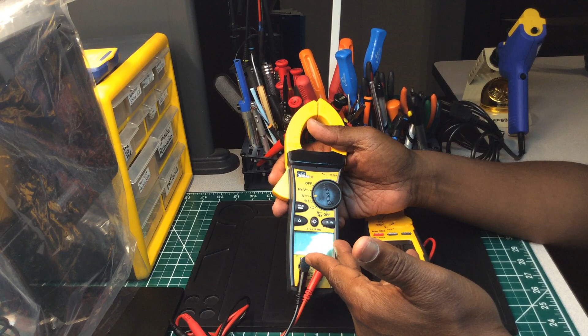You have capacitance, ohms, continuity, amps, and hertz, and relative mode. You have min max, hertz, and capacitance again — that's the selector switch right here. You have inrush here on the side, that's something I would use testing motors or whatever I'm testing — technical inrush measurement.